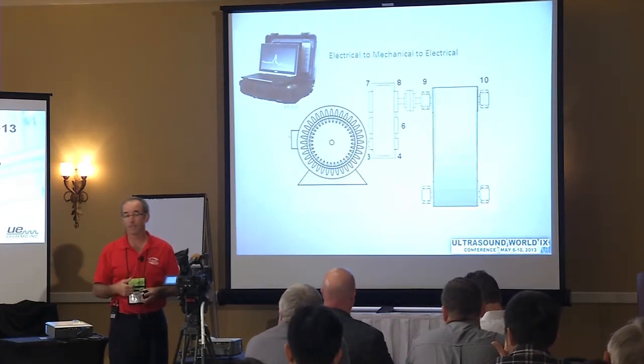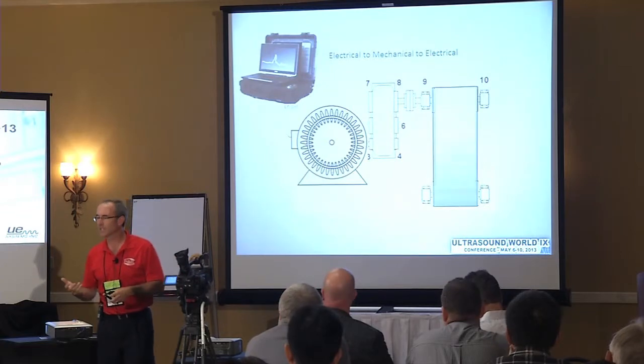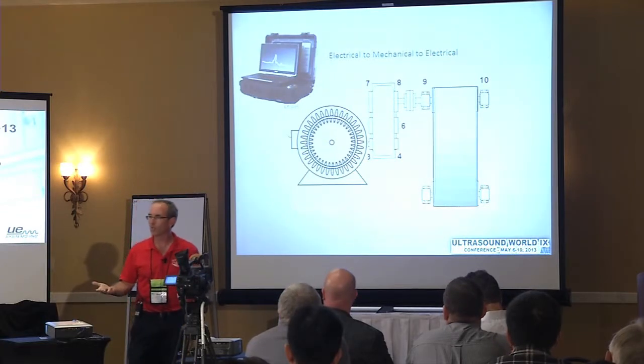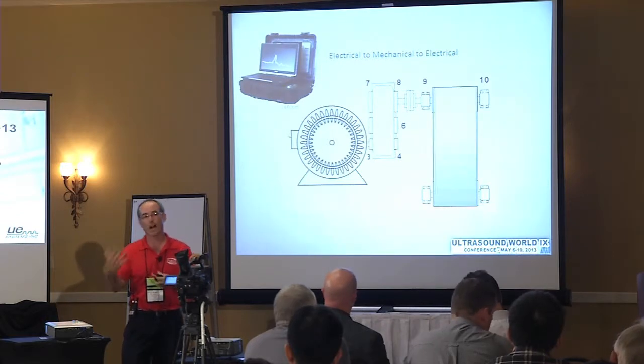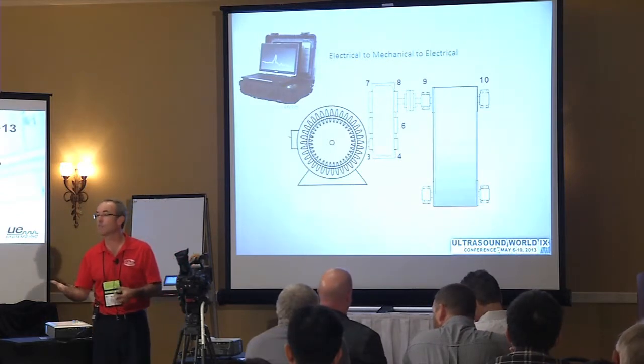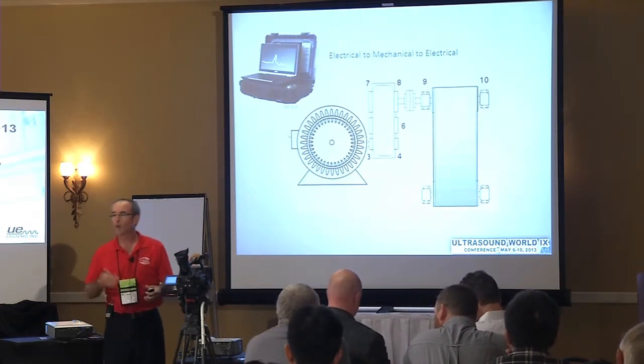This was a belt-driven fan. So they go out and say, yeah, you know what, it was misaligned. But they had just aligned it, so why were we seeing that? Well, they had aligned it cold. So when they went back to check it again, hot alignment changed it quite a bit. So they were able to get that done.